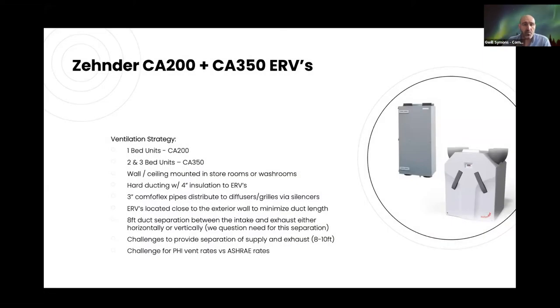The strategy: one-bed units use the Zehnder CA200s, and larger two- and three-bed units use the CA350s. HRVs are stored in washroom or storeroom ceilings. Hard ducting to the exterior uses four inches of insulation, and three-inch ComfoFlex pipes distribute within suites via drop ceilings. There's the typical challenge of trying to get the ideal eight to ten feet of separation between supply and exhaust, though we question whether that's truly contamination when it's air from your own suite. We're also hitting the challenge of meeting PHI ventilation rates while making ASHRAE work.